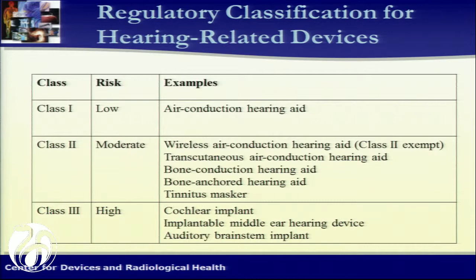In the Class 3, the high-risk type of auditory devices, we have things like cochlear implants, as you might imagine. We have certain implantable middle ear hearing devices, the most recent being the Envoy device, which some of you might be familiar with, a totally implantable middle ear hearing device, and things like auditory brainstem implants. So again, we have the complete spectrum of devices within hearing-related technologies. Okay, so now getting back to the Class 1 garden variety air conduction hearing aid, and that's really the focus of this workshop, so that's where I'm going to spend most of my time in terms of the regulatory controls that we have in place for those technologies. So again, they are Class 1 devices, and FDA has determined that general controls in and of themselves are sufficient to ensure safety and effectiveness of the air conduction hearing aid device type.